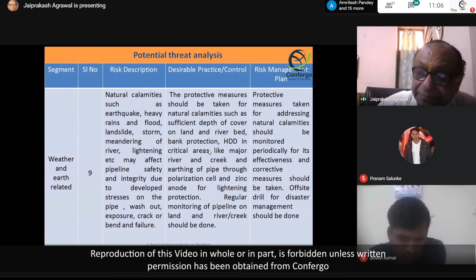And then you have lightning or earthquake. For earthquake we have discussed that you can have more cover, more thickness of the pipeline, or more coating thickness. For lightning, you have the polarization cell and the zinc anode, where the lightning surge is put to the ground, so that it doesn't affect your coating or damage the pipeline. The lightning surges, the high potential and high current because of the lightning, go to the ground through the polarization cell and the zinc anode.